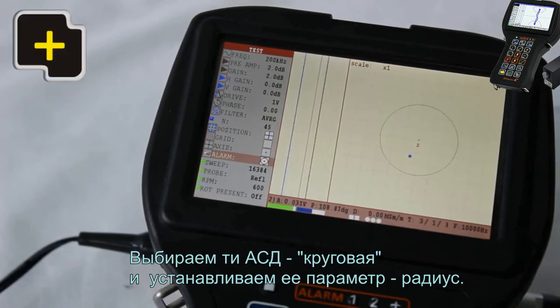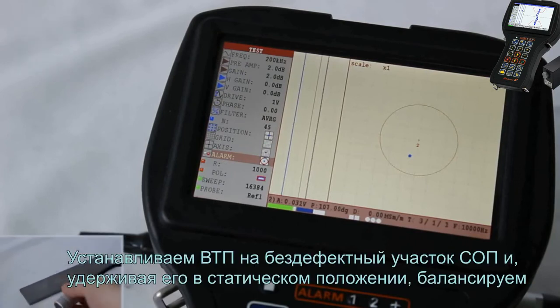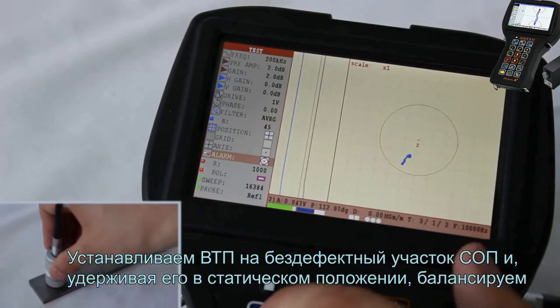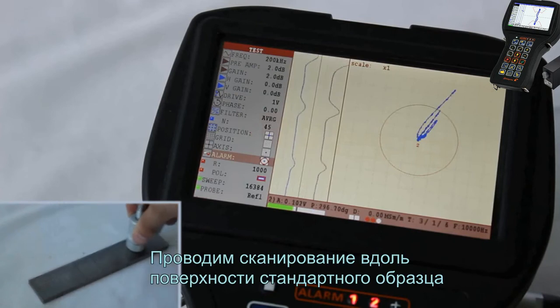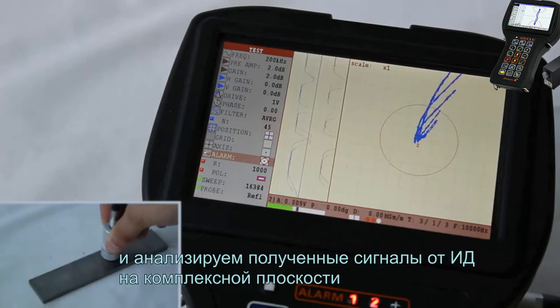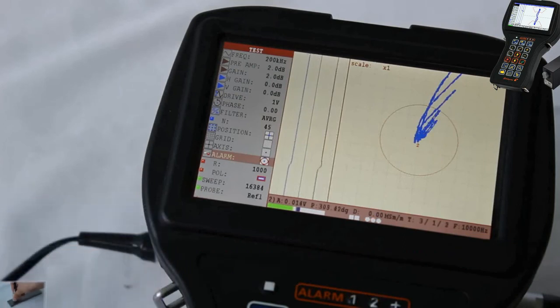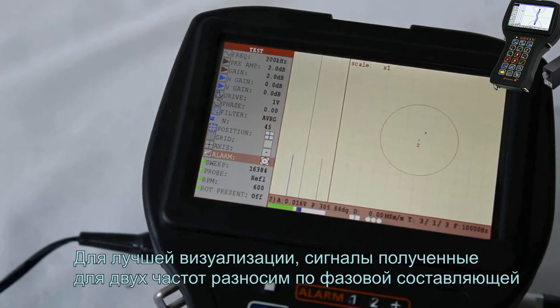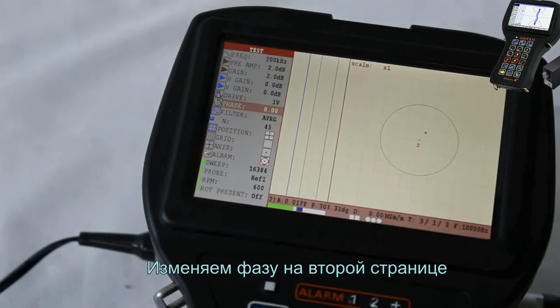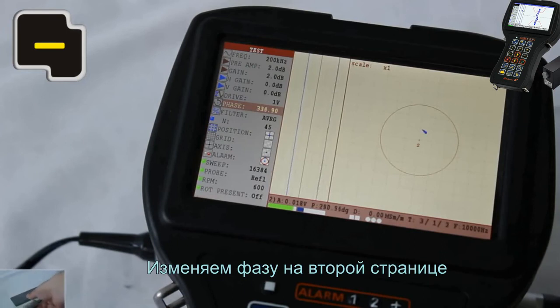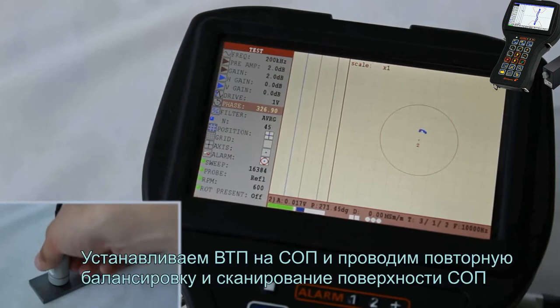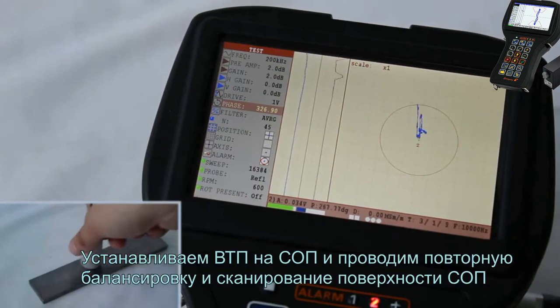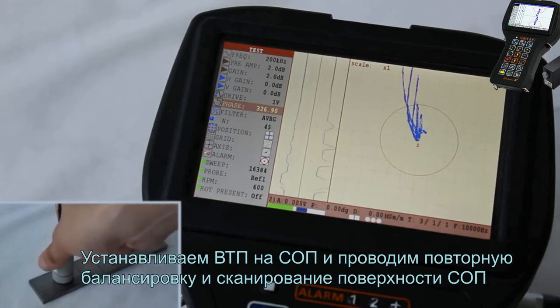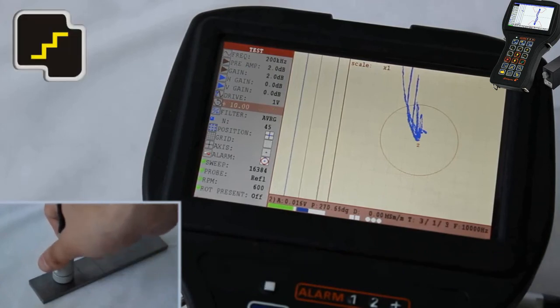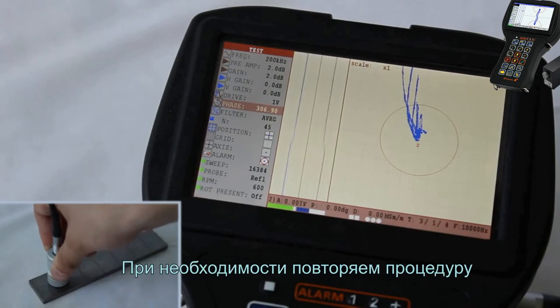Select the type of alarm, circle, and set up its parameter, radius. Place the EC probe at a flaw-free area of a block and by holding it in a static position, perform the balancing. Carry out the scanning along the block surface and analyze the signals received from artificial defects in a complex plane. To improve the display visualization, the signals received for two frequencies are to be placed over the circle. Change the phase on a second page. Place the EC probe at a block and perform the repeated balancing and scanning of a block surface. If required, repeat the procedure.